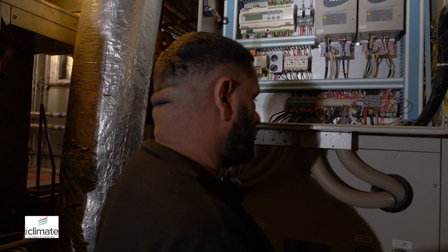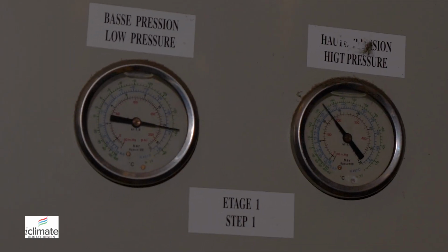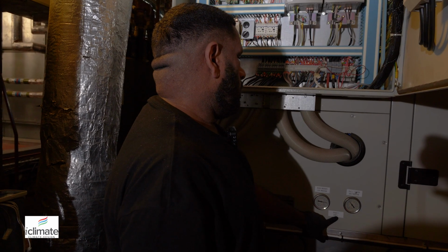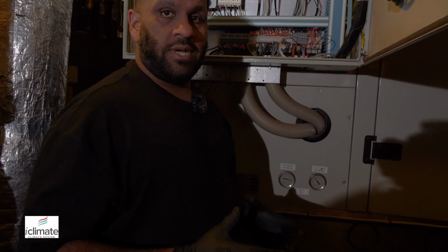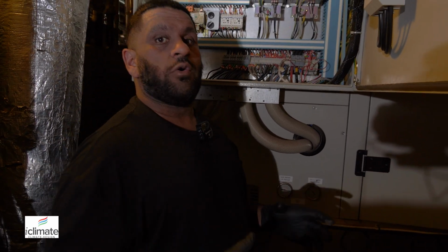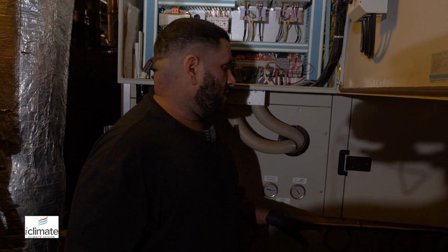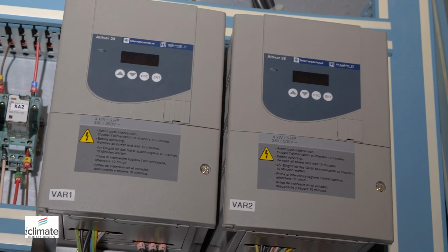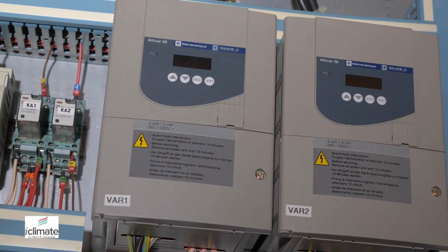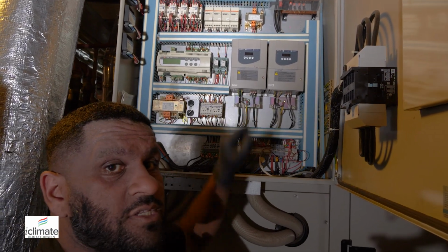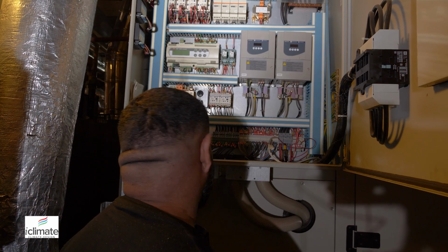So this is what we're back to, having two circuits. They call it a step 1 and a step 2. A step 1 will be possibly a different size compressor and a circuit, which would deal with the majority of the load that's coming back. When this gets to 100% diversity, i.e. VAR 1, the compressor runs at full amps and the inverter runs, and then the water temperature is still not hitting the supply temp and the return temp is still kind of high. After a period of time, it will then set up the step 2.